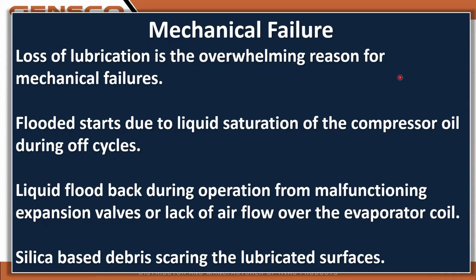Mechanical failures: loss of lubrication is the overwhelming reason for them. That could be due to a flooded start, or it could be due to liquid flood back while it's operating, which would be caused by malfunctioning expansion valves, overfeeding refrigerant, or lack of airflow over the evaporator coil, which would eliminate any superheat coming back to the compressor. And it's also caused by silica-based debris scarring the lubricated surfaces.